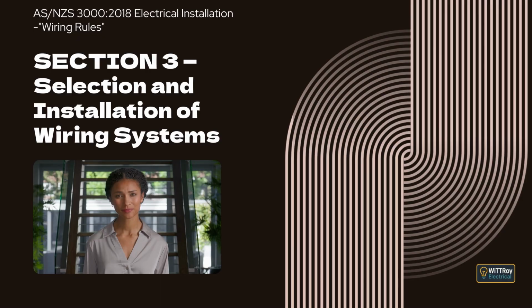Clause 3.3 External influences. This clause introduces the idea that wiring systems must be able to work safely and properly under the environmental and other conditions they are likely to face at the place of installation. Clause 3.3.1 General. This clause explains that wiring systems must operate safely and function as intended in the conditions they are exposed to. Protection against environmental and other influences can be achieved through suitable design and construction of the wiring system itself, or by adding extra protective measures as part of the installation, as long as those measures do not interfere with normal operation. Clause 3.3.2 Particular influences.